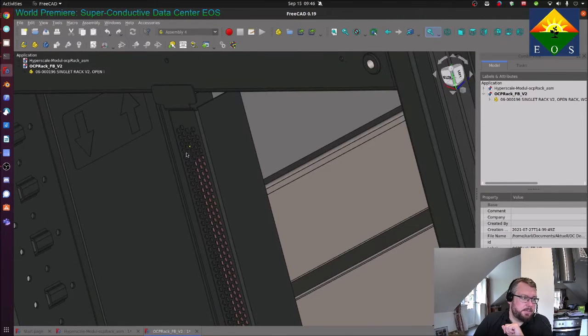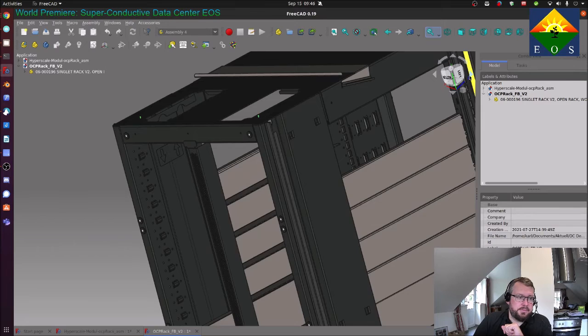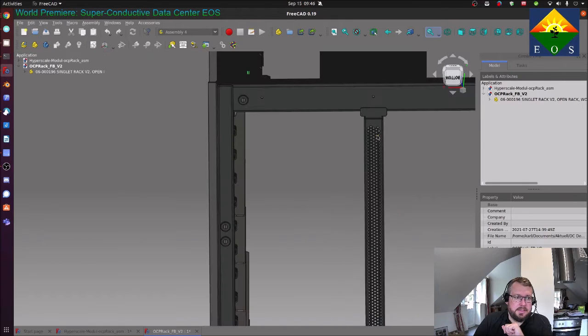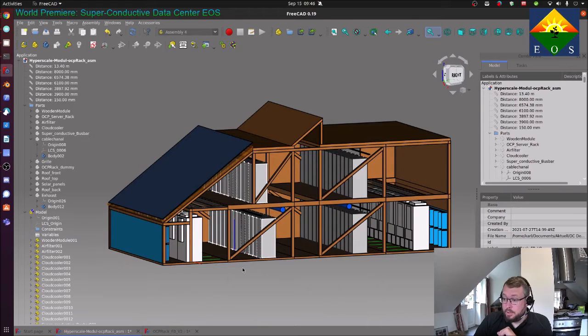You have the central busbar here with a ground and a positive busbar showing, and this is directly connected with so-called tap-offs to the superconductive busbar, eliminating each and every power shelf. A 100 megawatt data center without a single power shelf in the rack, resulting in a 30% higher density per rack.